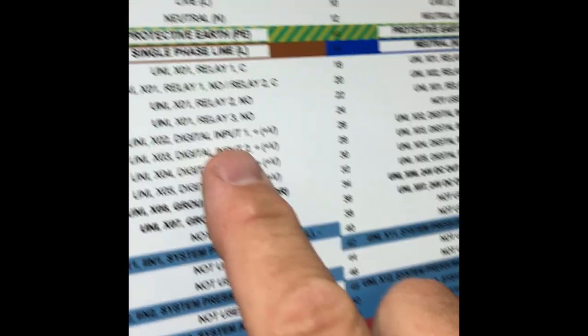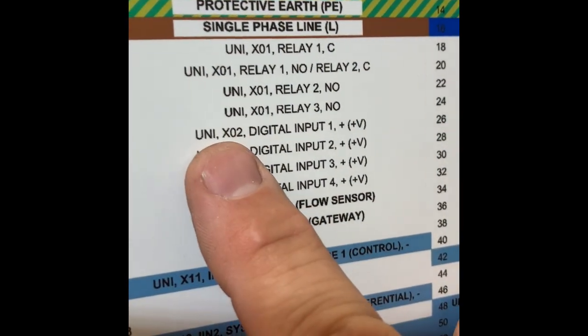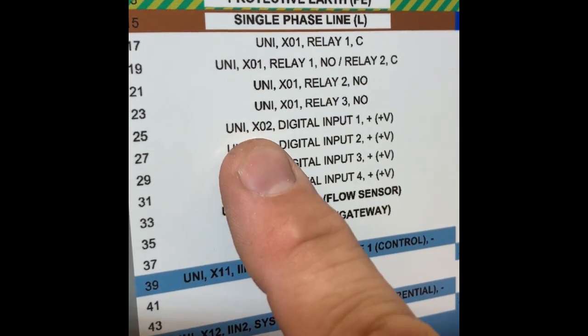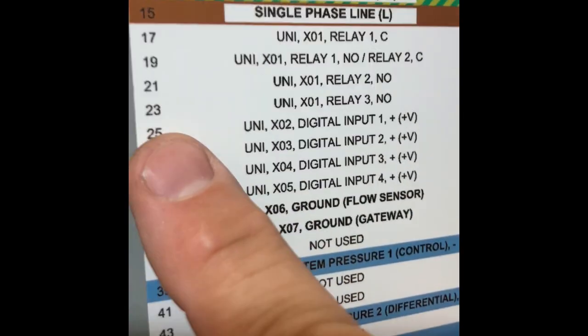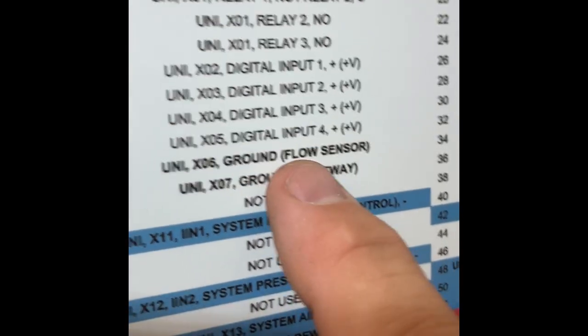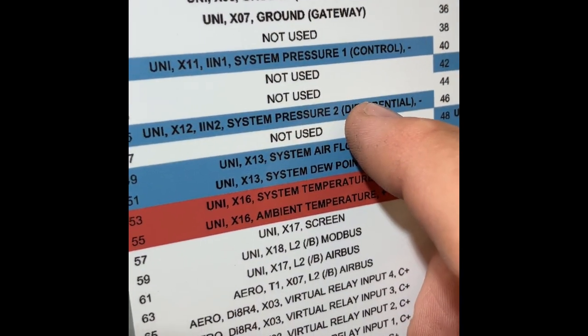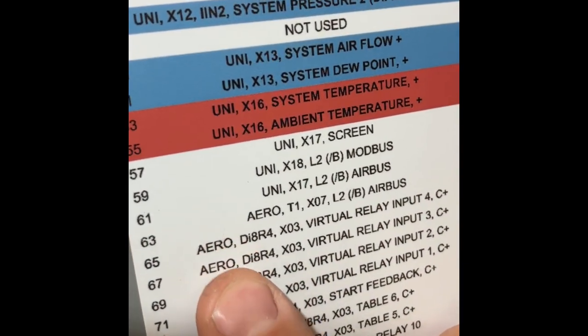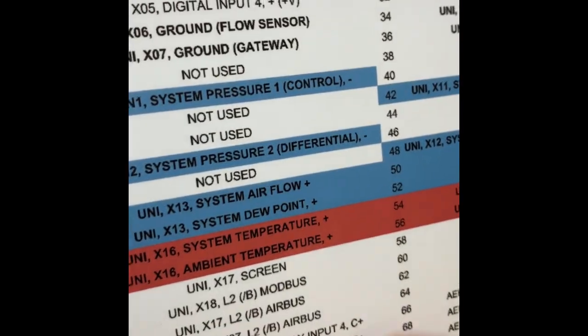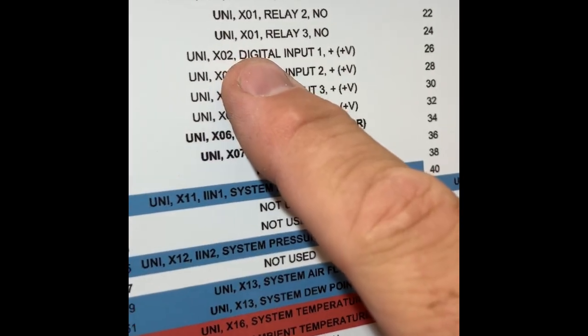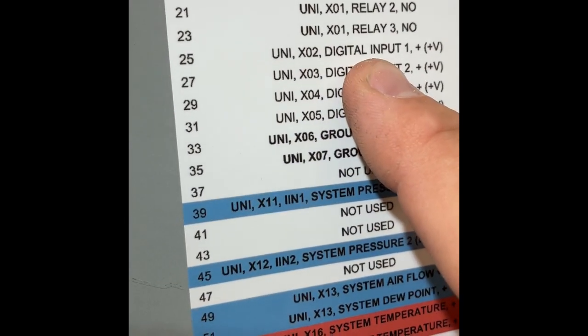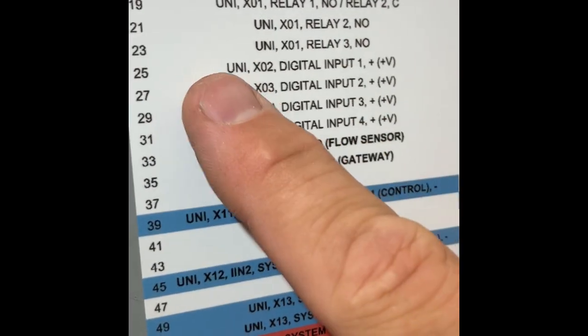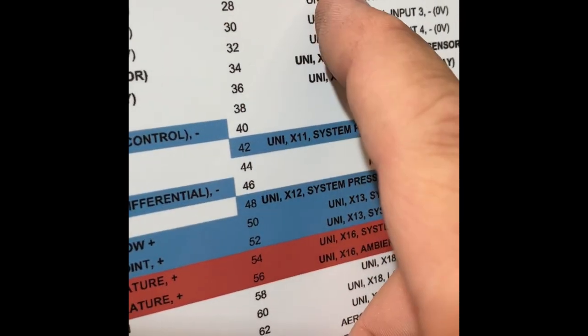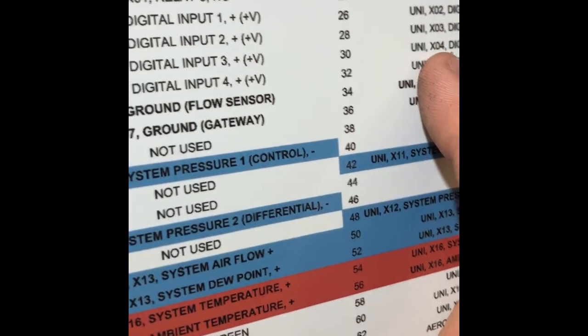And so for example, our dryer inputs are going to be up here. Anytime you see uni, that's short for the unitag. That's telling you that this terminal 25 here is wired to the unitag. Then you'll have ones that are part of the actual Aero system, and you have ones that are the unitag. But for example, one of our dryers, say dryer number 1, the fault is going to be on digital input 1. So our plus is going on 25, our minus is going on 26. It's literally that simple.